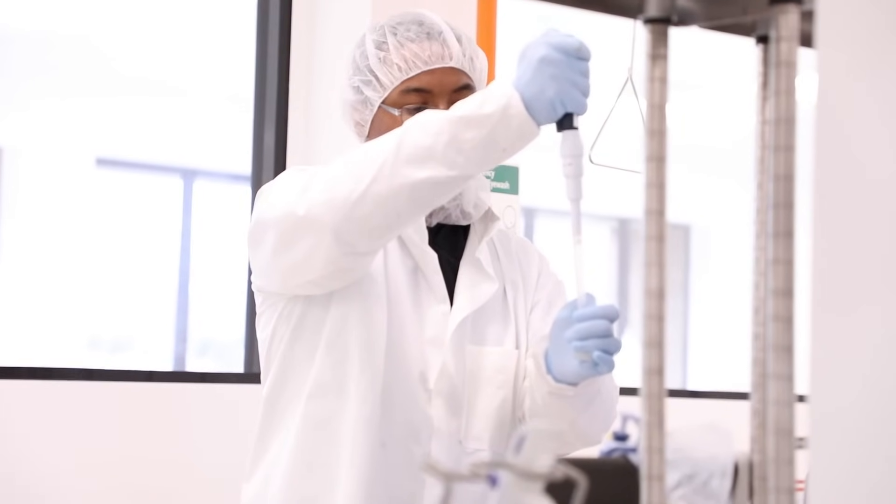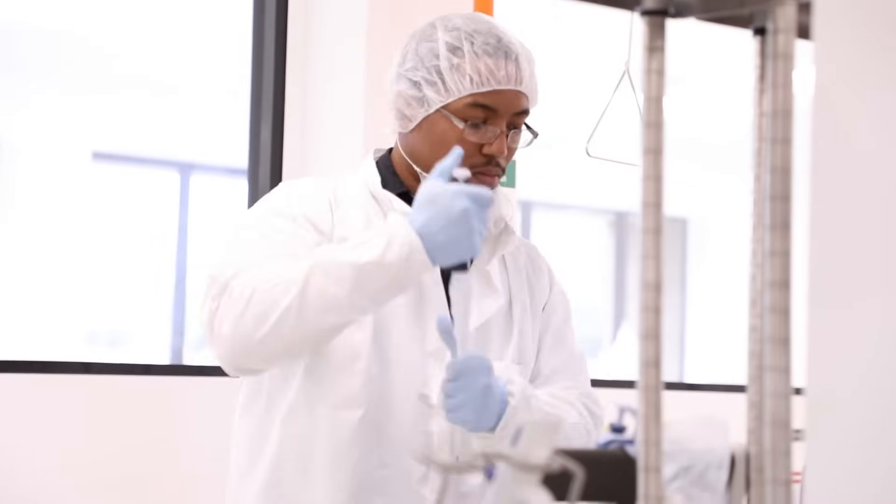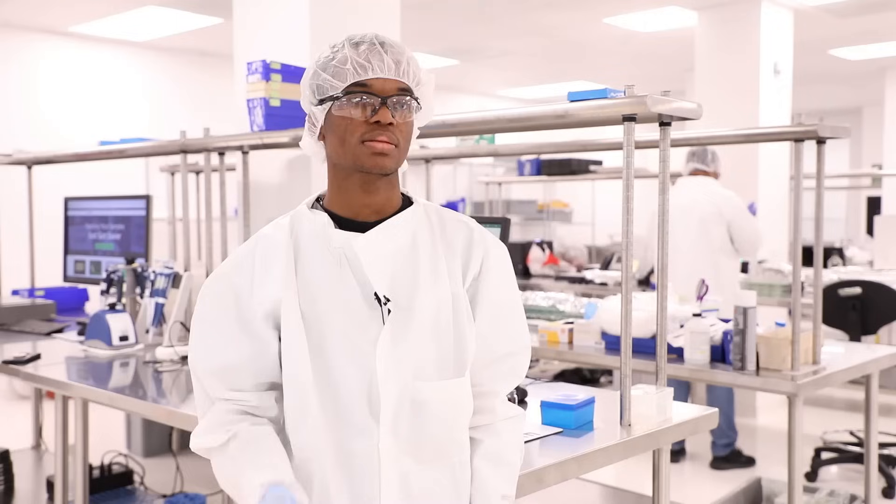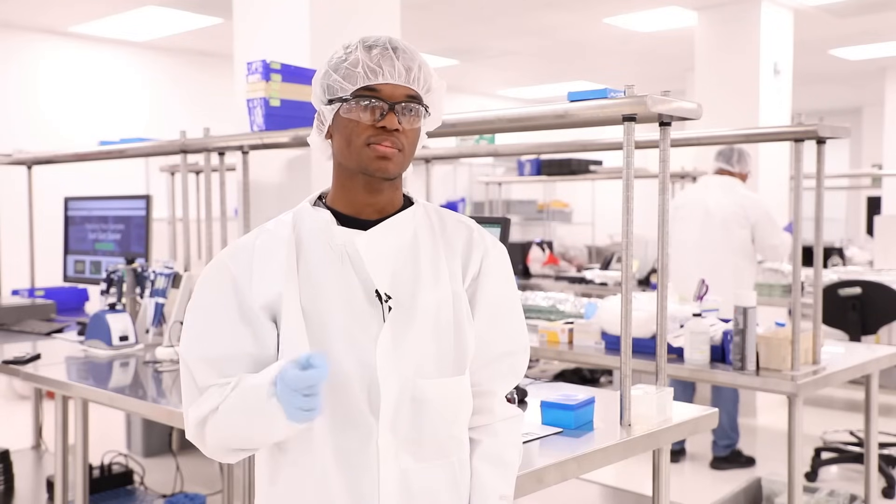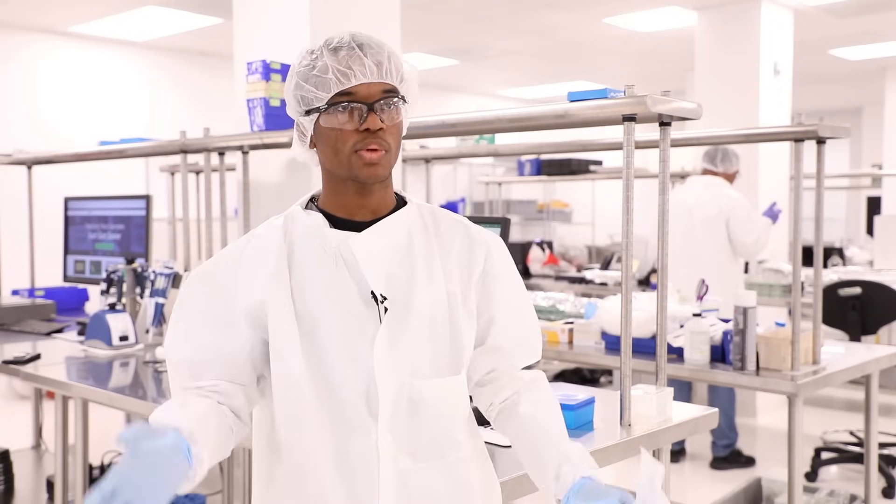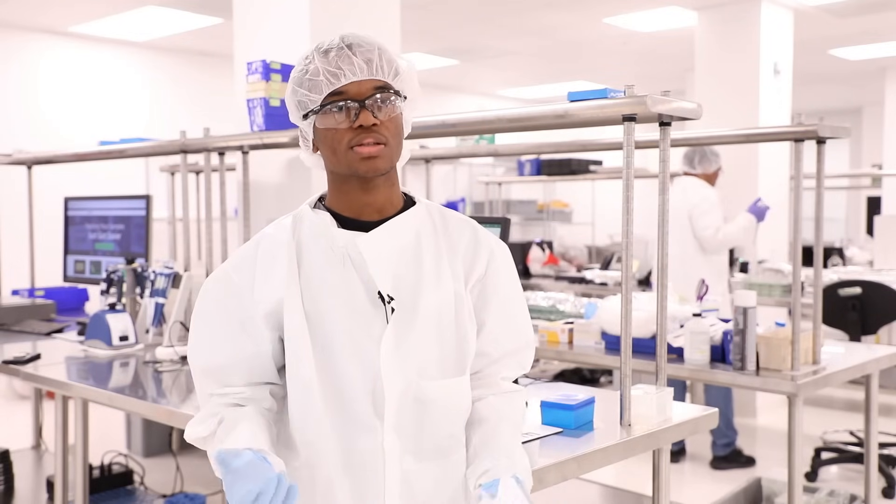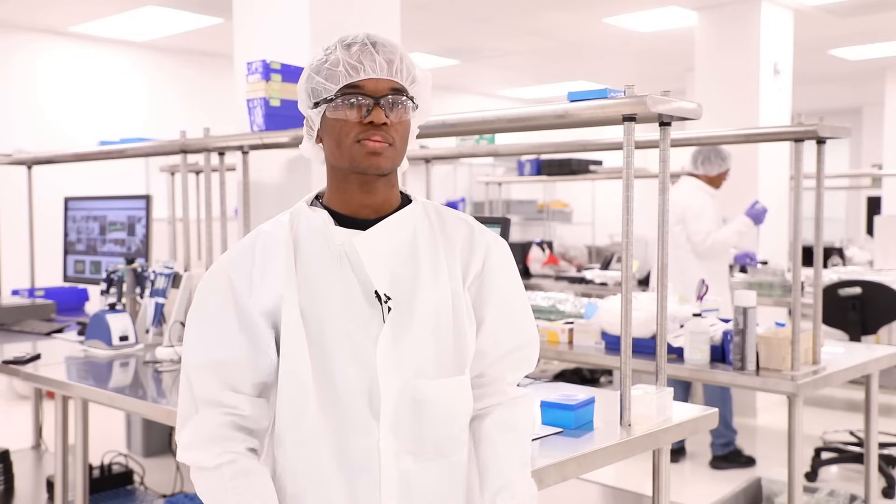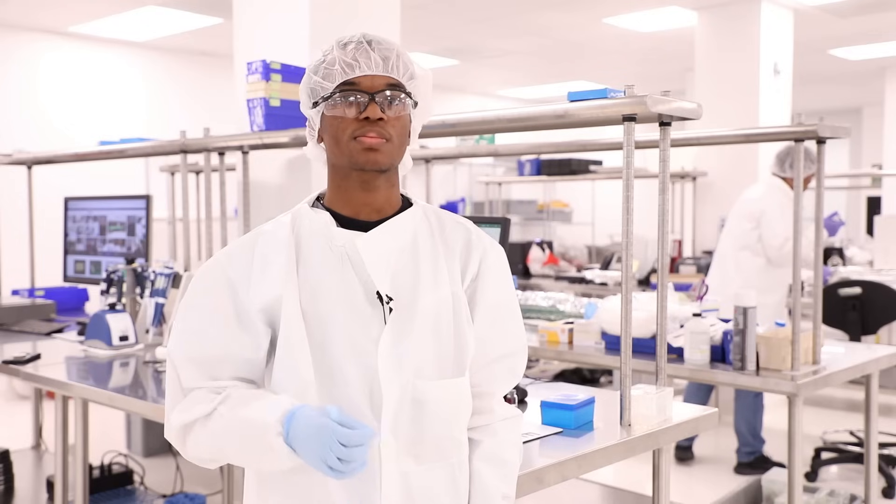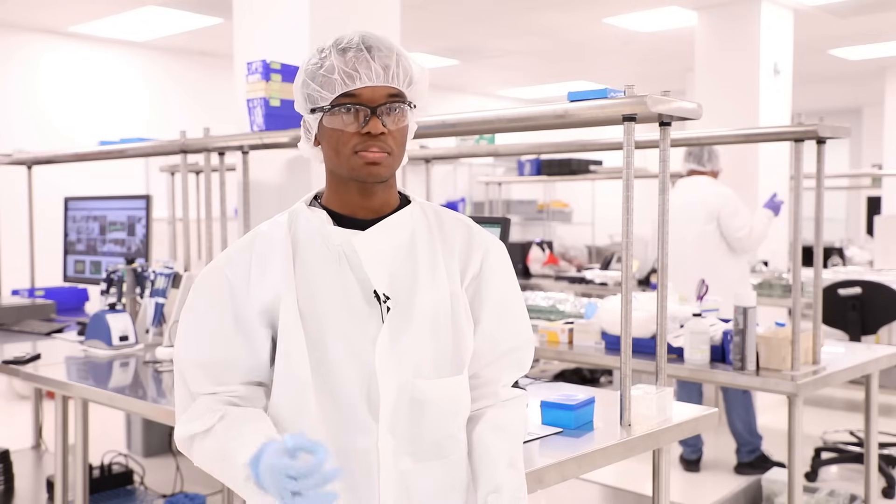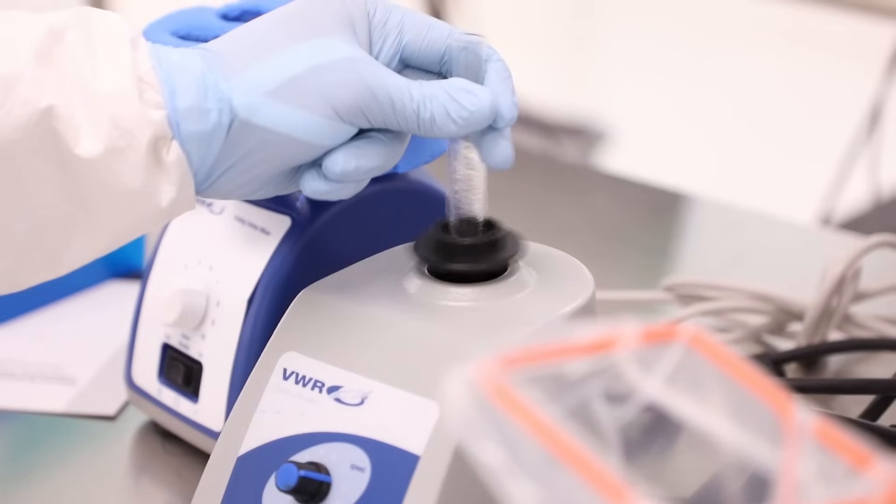And upon contact with endotoxins, it causes a coagulation reaction. So the test itself, the instrument, measures when the coagulation reaction occurs. And with that, we can actually detect up to 0.001 EUs per mil, making the test very specific and sensitive.